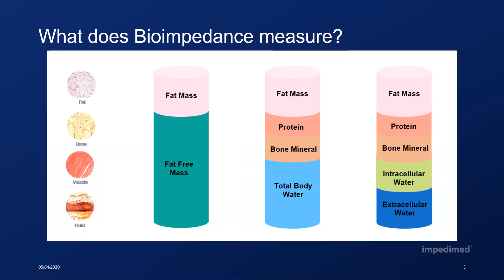Different types of tissues all have different electrical properties, which is determined by the composition of the material. Electrical current will always flow through the path of least resistance. In the case of biological tissue, fat and bone act as insulators and do not conduct significant current. Fat-free mass and fluids, on the other hand, conduct current via ionic conduction, and the applied current will therefore pass through lean tissue, muscle, and electrolytic fluids such as blood and lymph.